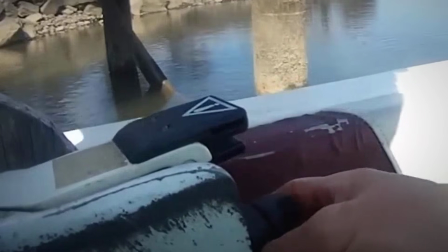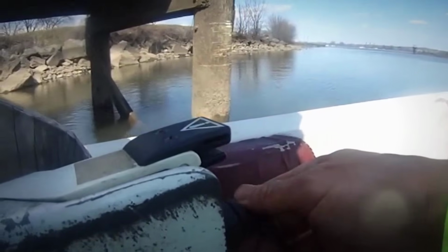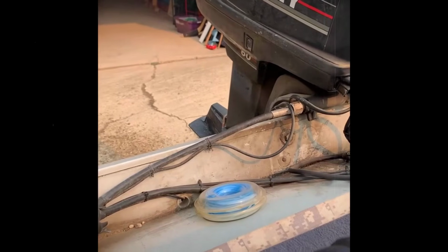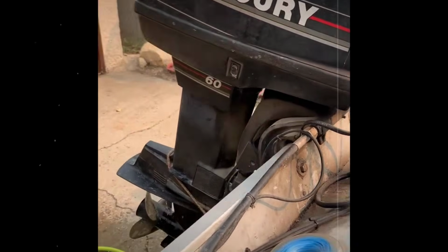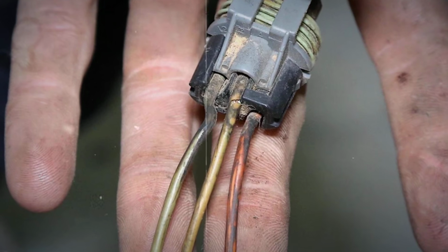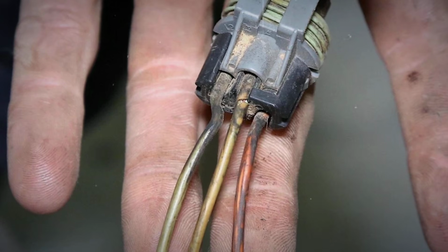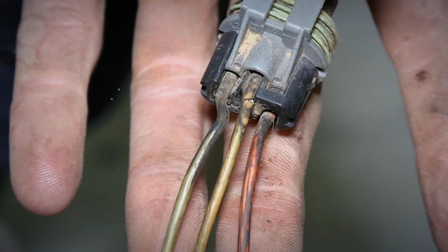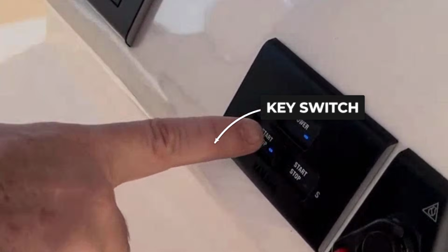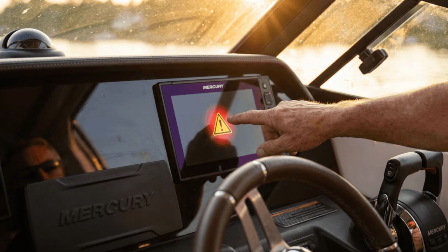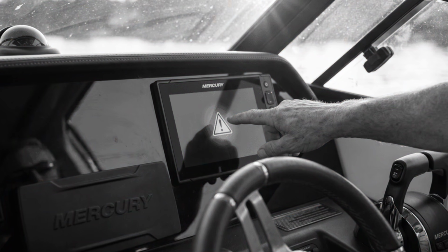The overheat horn screams, but the motor's not actually hot. The telltale stream is strong and the power head's cool to the touch. A stuck stored overheat code or a glitchy temperature sender will hold that alarm hostage. First, always confirm it's a false alarm and not a real overheat. If in doubt, shut down.